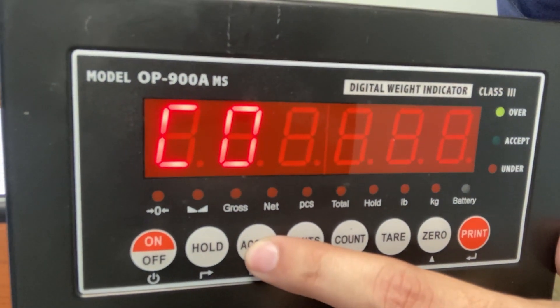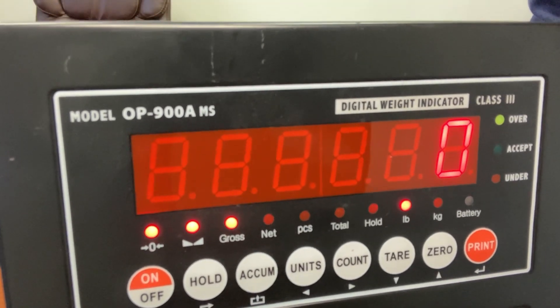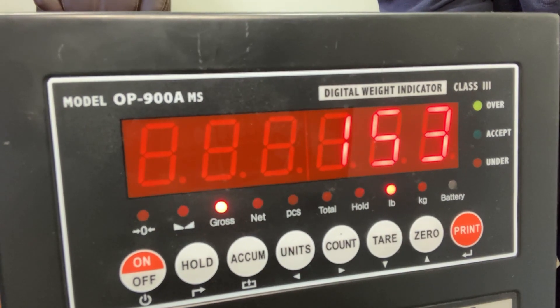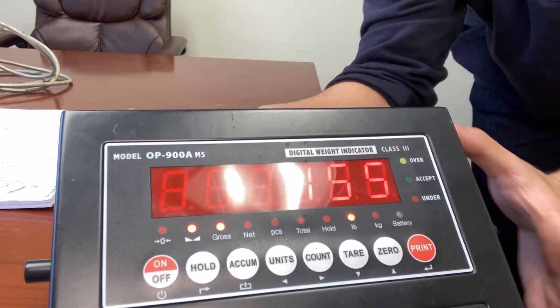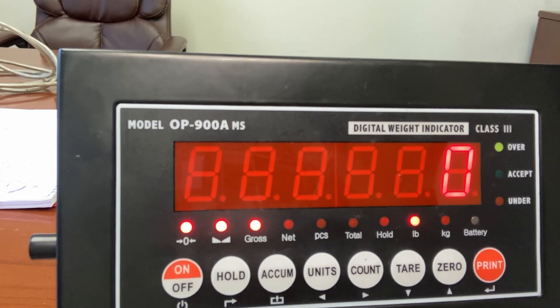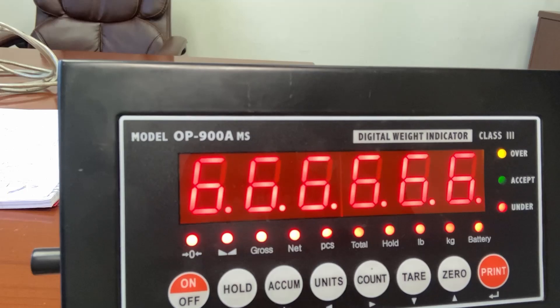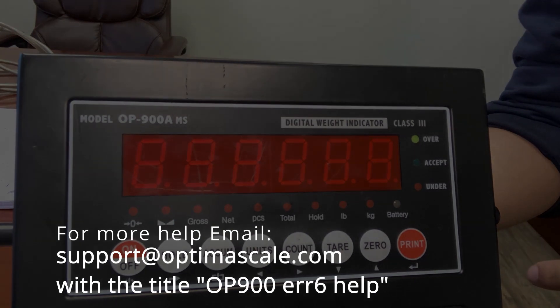Press print and you'll see C07 — that means you're done with calibration. To save and exit, press the ACCUM button. Your scale should go to zero, because there's nothing on the scale. Now test it out. One common question is: will the calibration save if I turn it off? Yes — if you turn it off and back on later, your calibration will save, so you don't have to do this process again. This should help you with calibrating and fixing your error 6 issue on the OP900.